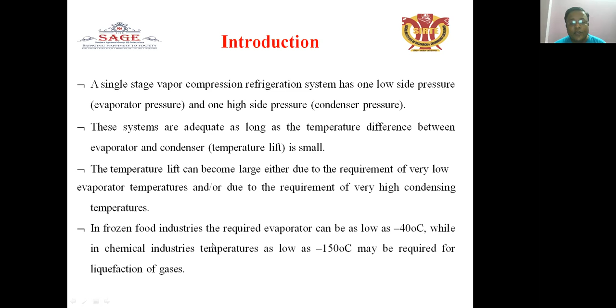The liquid removes a high amount of heat to the surroundings. In frozen food industries, the required temperature can be as low as minus 40 degrees centigrade, while in the chemical industry the temperature can be as low as minus 150 degrees centigrade. It may be required for the liquefaction of gases. Such temperatures can be achieved when the multi-pressure vapor compression refrigeration system is installed, giving a chance of achieving the lowest temperature for the chemical industries and for the liquefaction of gases.